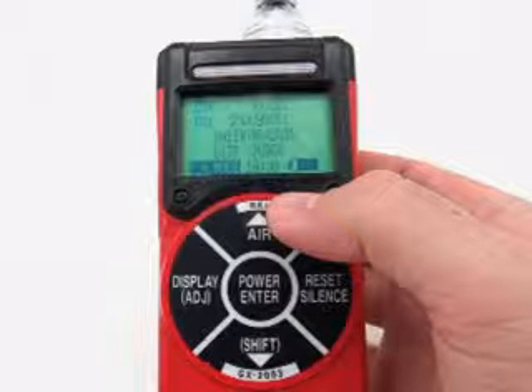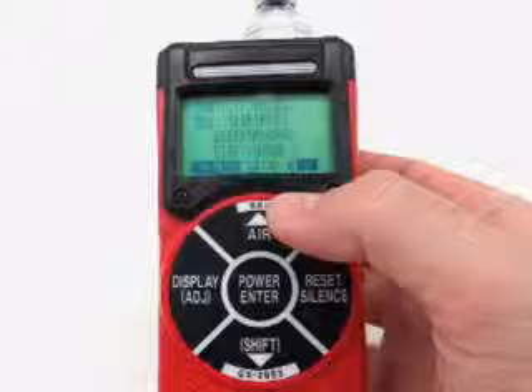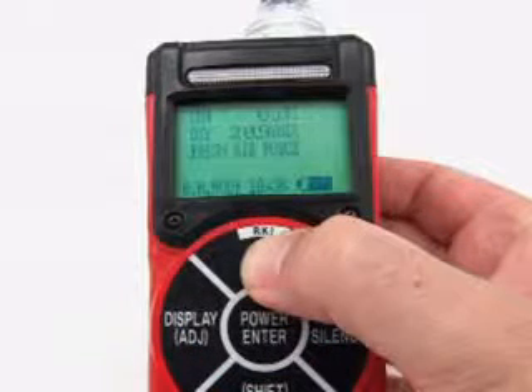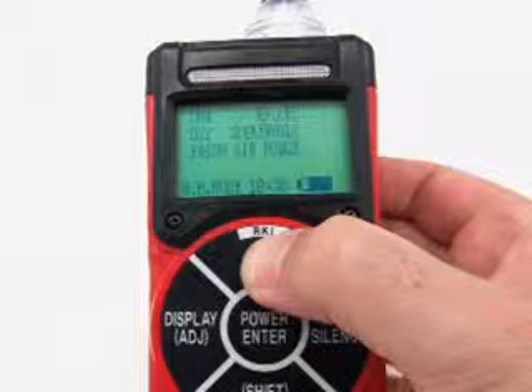Find a fresh air environment. This is an environment free of toxic or combustible gases and is of normal oxygen content, 20.9%. Press and hold the air button. The pump will start and the display will indicate Fresh Air Purge below the oxygen reading for a few seconds before indicating that a demand zero is taking place and prompting you to hold the air button.